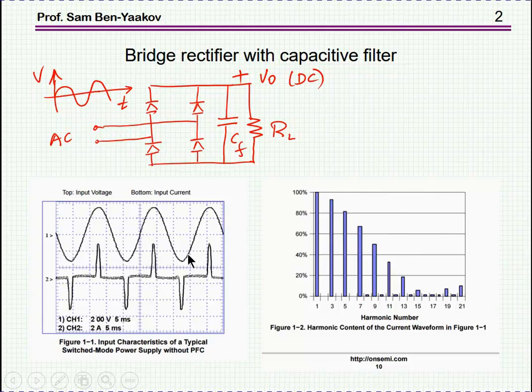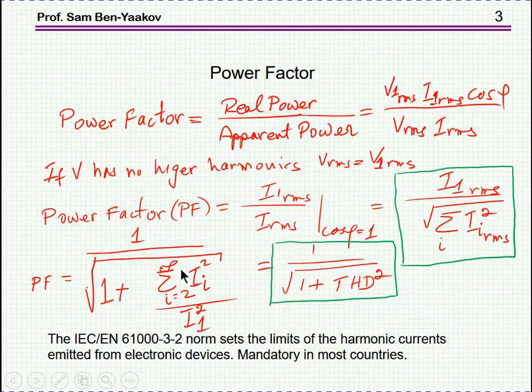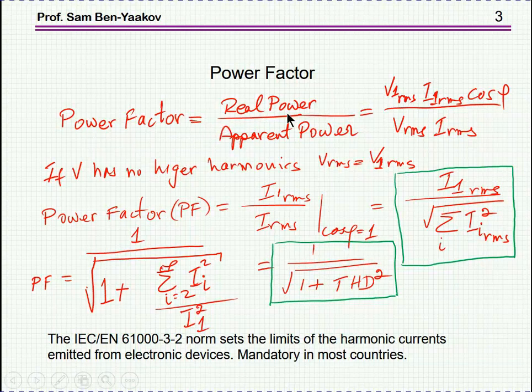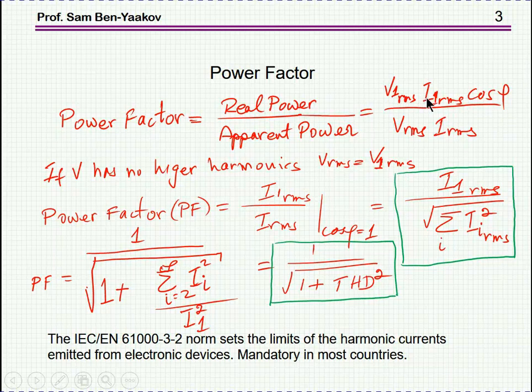Before going into the detail of how this can be done, let me define what power factor is, so we can understand the problem at hand. Power factor is defined as the ratio between the real power and the apparent power. Real power is the first harmonic of the voltage times the first harmonic of the current, times cosine phi, if there is a phase shift between these two. The total, or apparent, power is the RMS voltage times the RMS current.